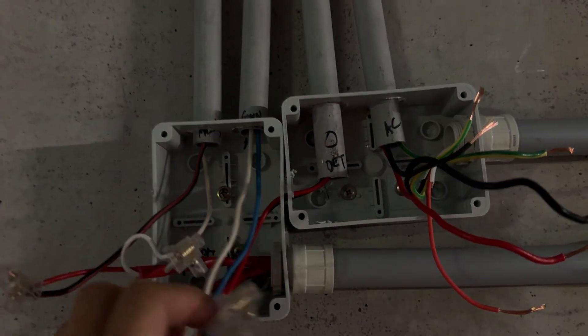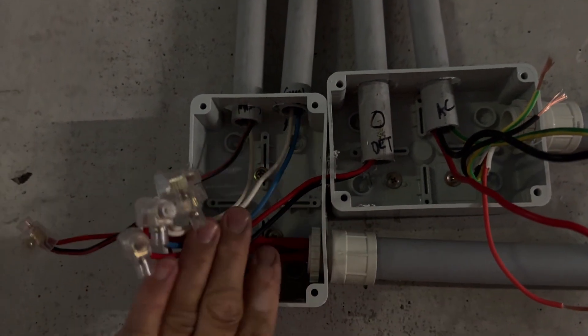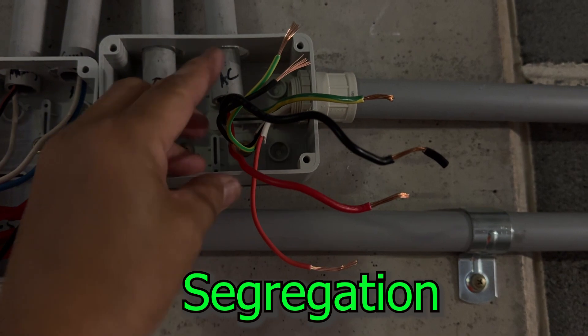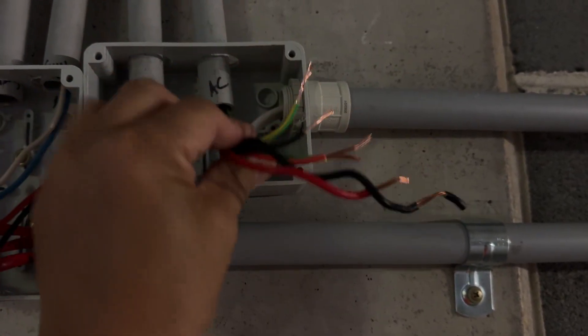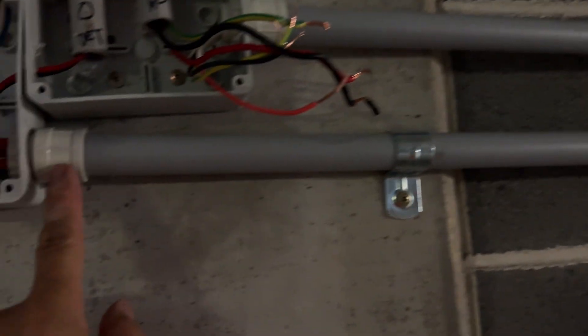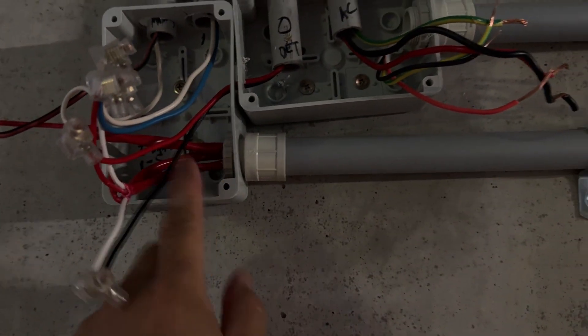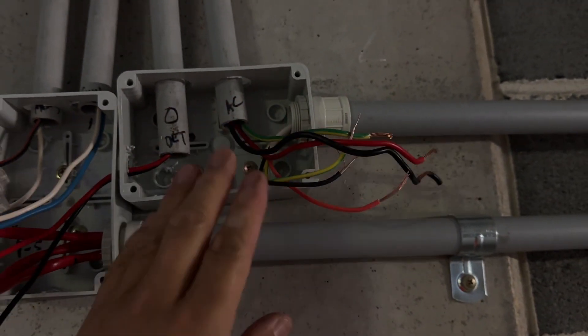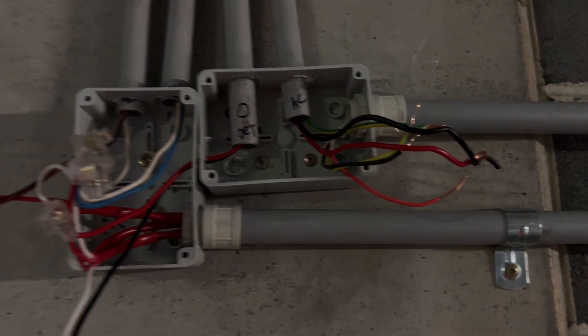Now you will notice that these are all my detection side, the 24 volt DC, and my 240 volts AC always has a separate conduit. That should be separated from the rest of the extra low voltage. Take note, if you are not an electrician, you're not allowed to do the 240 volts. You must be an electrician, a licensed electrician.